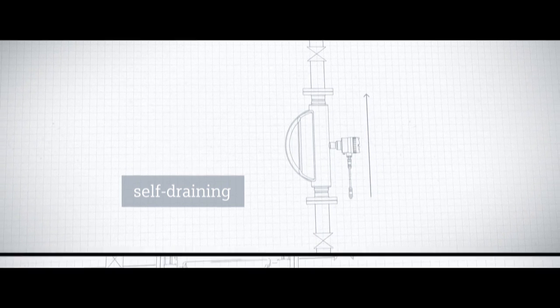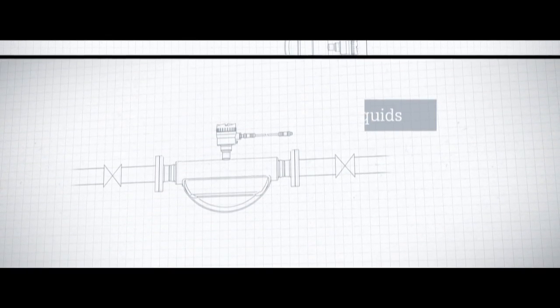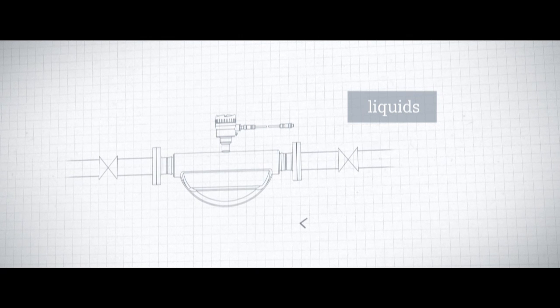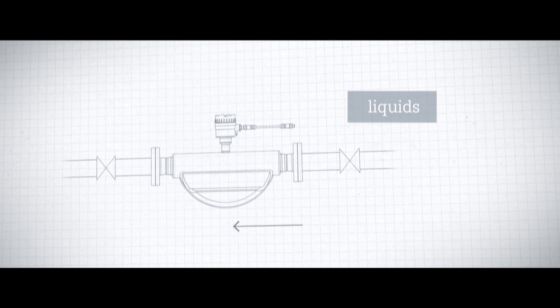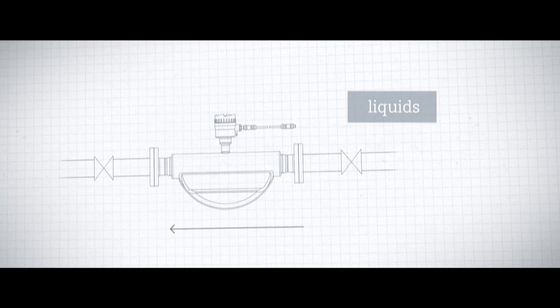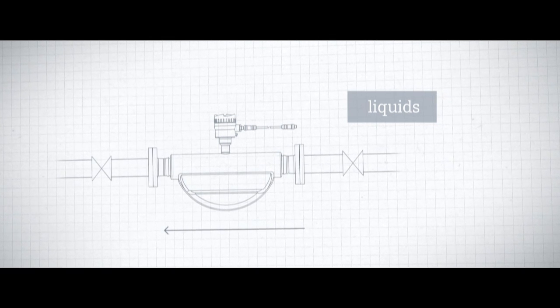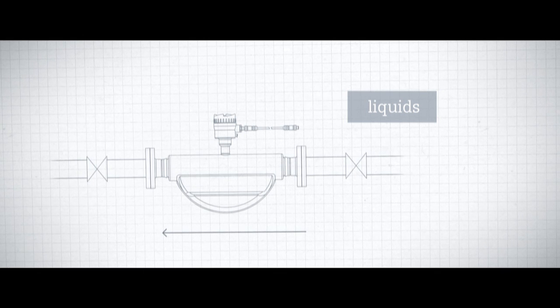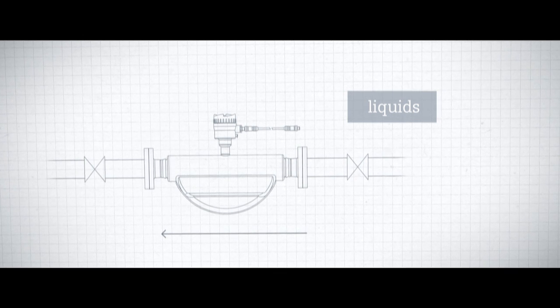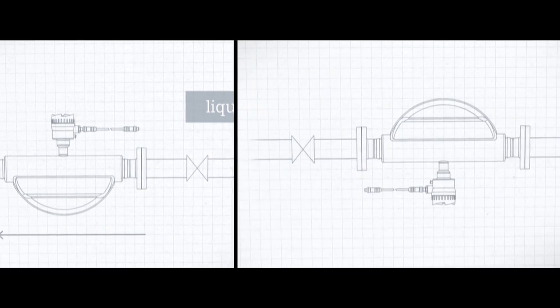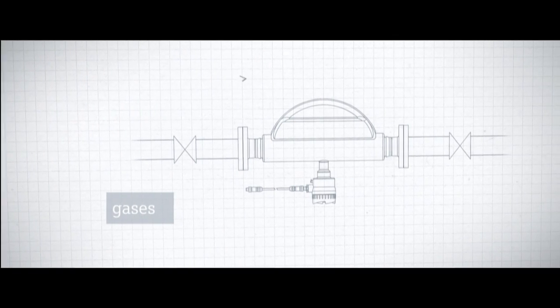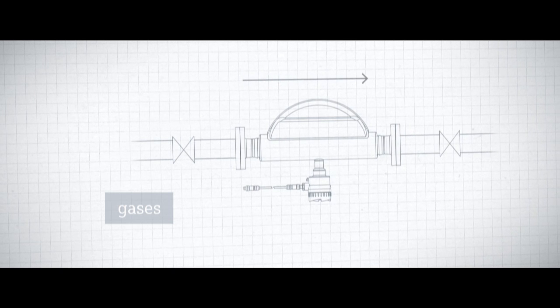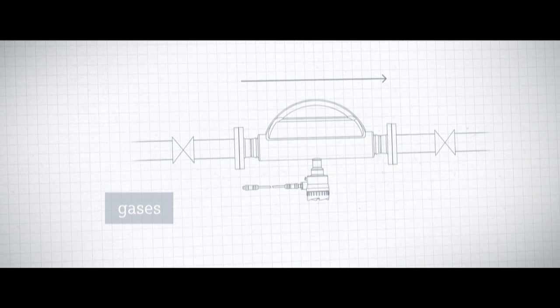For liquid applications, we recommend a horizontal mounting position with the inner pipes of the sensor facing downwards. For applications involving gases, we recommend a horizontal mounting position with the pipes facing upwards.